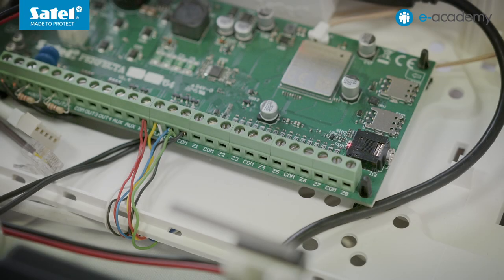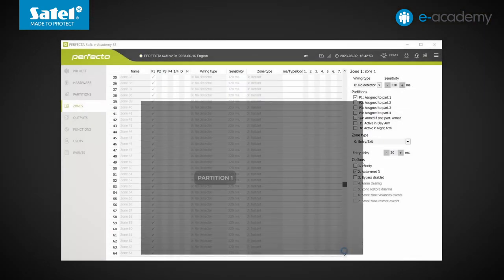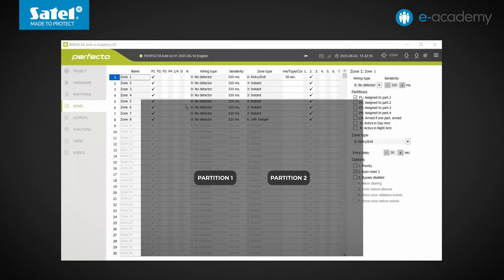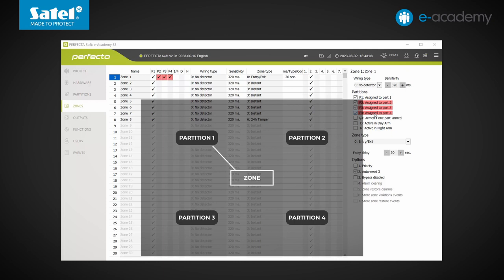There are 8 wired zones available on the electronics board and their number can be increased using INT-E expansion modules, of which up to 7 can be connected to the bus. Another new feature is the number of partitions to which zones can be assigned. Instead of 2, which are present on the older Perfecta models, twice as many — namely 4 partitions — are available in the Perfecta 64M control panel. Notably, each zone can be linked to 1, 2, 3, or even all partitions.